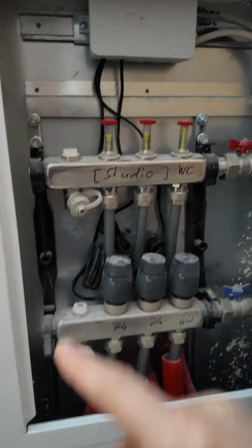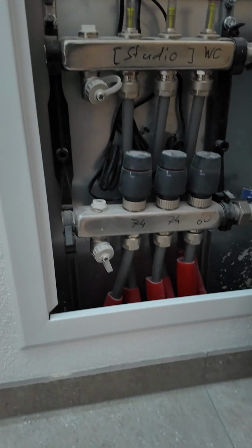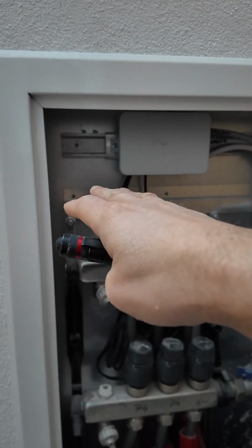The house that we live in is, I don't know, maybe up to 8 meters high or something. And so what they suggest is that the water in this circuit has got to be a certain number of bar, which means, okay, 0.1 bar can lift water up to 1 meter. So if the house is 8 meters, we really only need 1 bar, right? Because 1 bar can go all the way up to 10 meters of lifting the water. That's how they explained it to me. So we do have that amount of pressure in the system, but you can fill it up to 2 if you need to. Ours was leaking and it was going down, down, down from 2 down to 1.5, down to 1.3. But I guess even 1 should work.